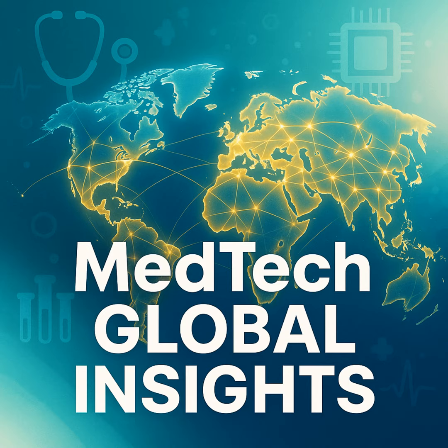Imagine you have a new hip implant. You can't just claim it's equivalent because it's made of the same titanium alloy. You must provide data comparing its surface coating, wear rate characteristics, and load-bearing capacity. You also need to demonstrate that any minor differences have no impact on clinical safety or performance, which is a very high bar to clear. Failure to do so often results in a demand for a full clinical investigation.